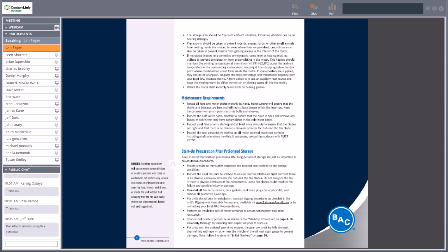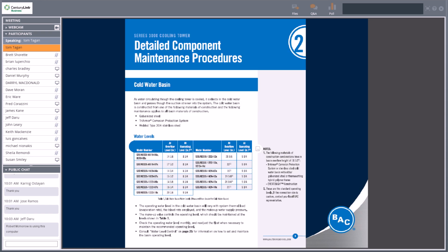But like I said, it goes step-by-step with instructions and maintenance requirements. On a monthly basis, it recommends turning the motor and rotating the fans, preventing any water buildup, things like that. Then startup procedures, preparation after that winter shutdown. Again, it's going to reference the startup procedures on the early pages of the O&M. It's going to talk about making sure that your bearings and motor are lubricated, checking water levels, and rotating and bumping your fan motor, making sure that your fans are not cracked, making sure that everything's pitched properly.